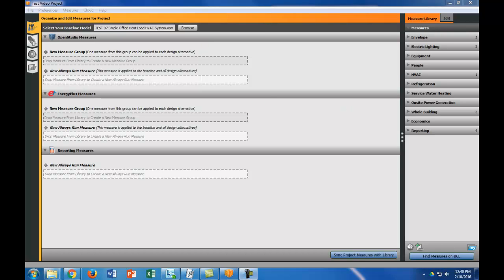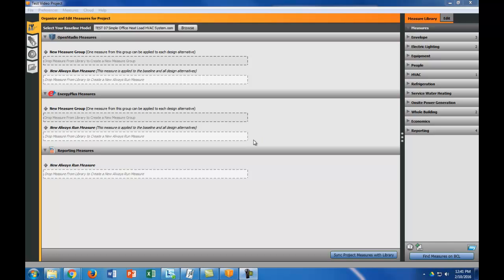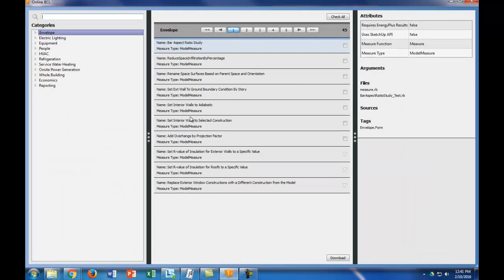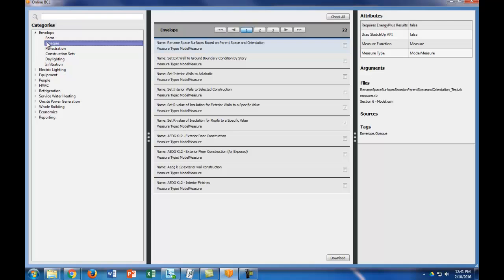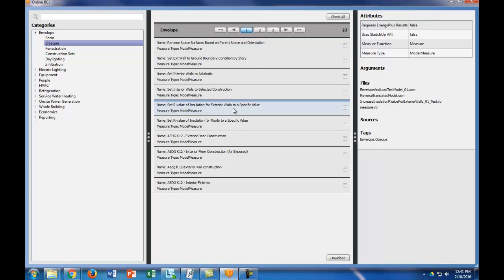Now that our baseline model came through, we're actually going to create some measures here. All the measures are going to do basically is modify this baseline model in order to compare the energy use to the baseline model. We can find these measures on the building component library. I'm actually going to do two different measures here. The first thing I'm going to do is an envelope measure, and I'm going to do the set R values of insulation for exterior walls to a specific value. This just allows you to change the R values of all the exterior walls, which is really nice. I already downloaded this, but if you haven't, you would click here and click download and it would download this measure into your parametric analysis tool.